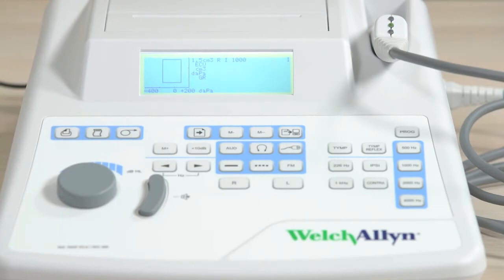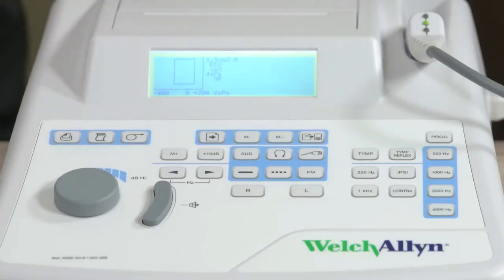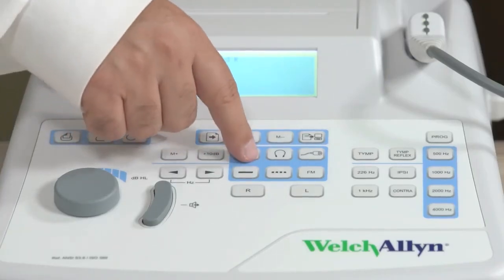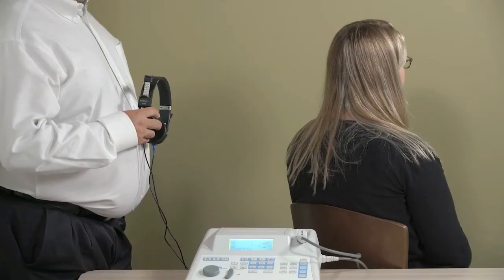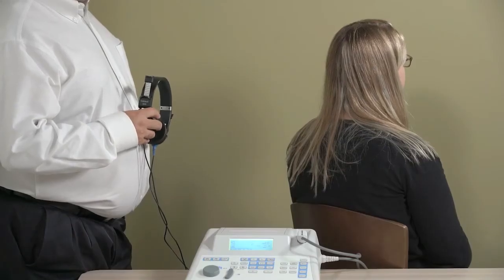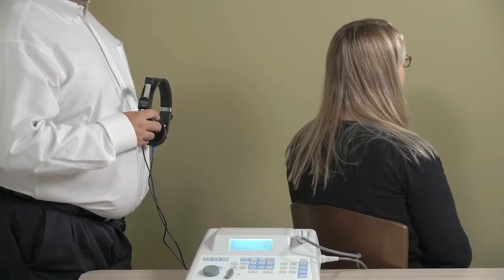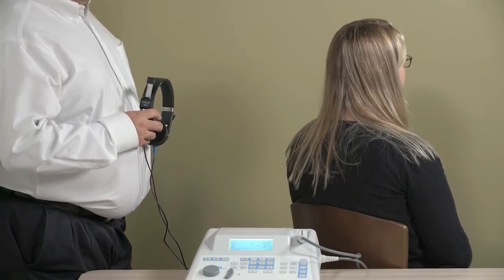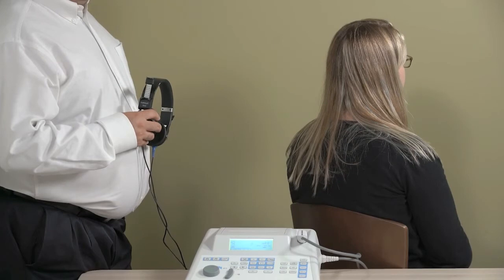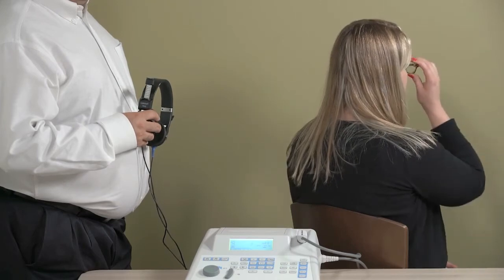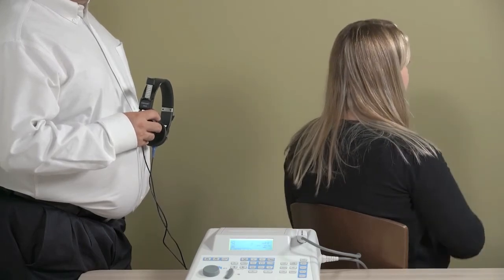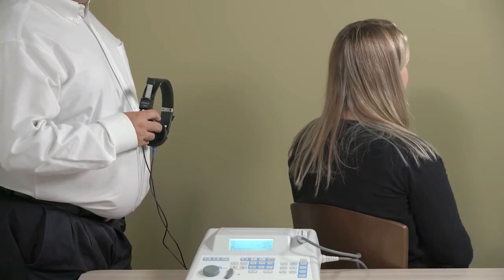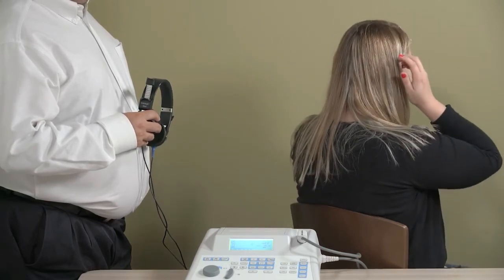To switch from audiometry to tympanometry, simply press either the aud or tymp buttons. Perform the test in a quiet room and seat the patient in a position where they cannot see you pressing buttons. The most important thing to remember is that a good seal is required between the earphone cushion and the patient's head and ears. Eliminate all obstruction between the earphones and the ears, such as hair, eyeglasses, earrings or hearing aids.